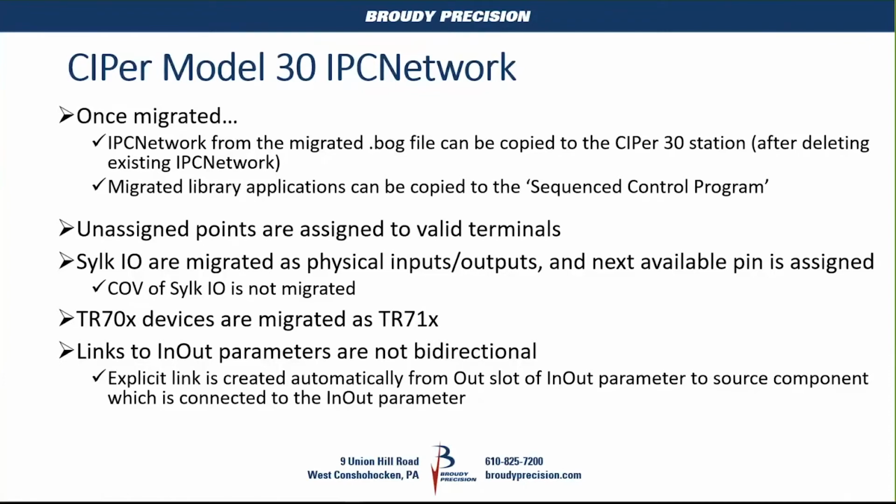The sequence control program folder is the folder where all of the CIPer 30 IPC components have to reside. Any of the Kit Control and any of the Niagara components can be within the sequence control program, but all of the Spyder logic will be placed underneath the sequence control program, and we'll go through that actually in the Workbench.